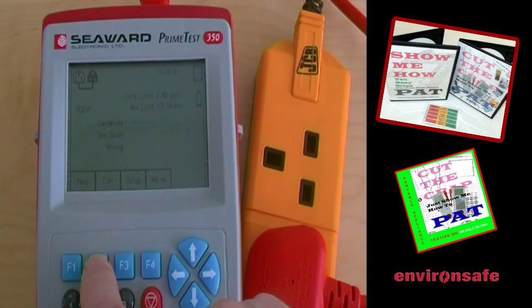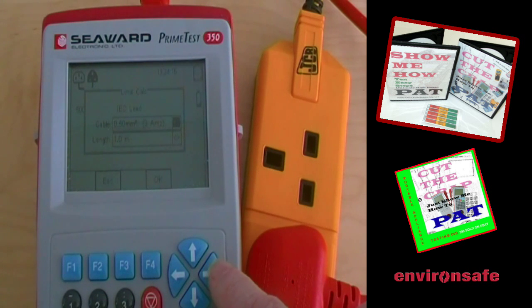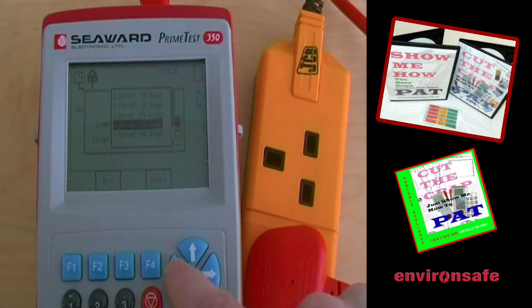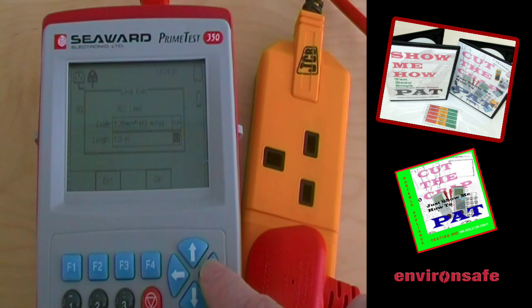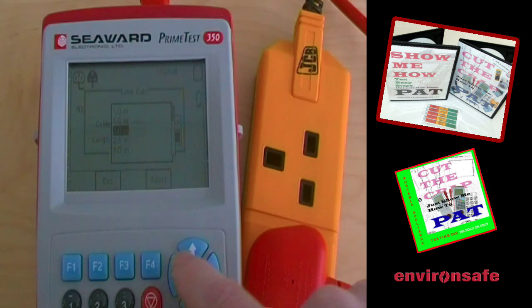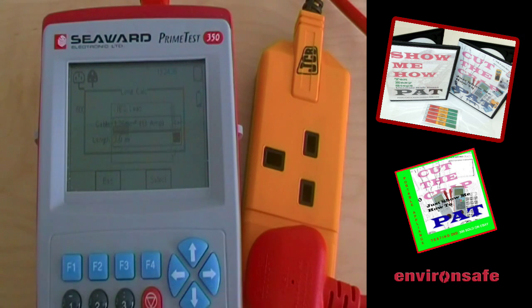Go into calculation, and the cable. It's 13 amp, so we'll go in 1.25 millimeters squared 13 amp. Select that. And the length of the cable is 2 meters. We'll select that, and we will OK that.